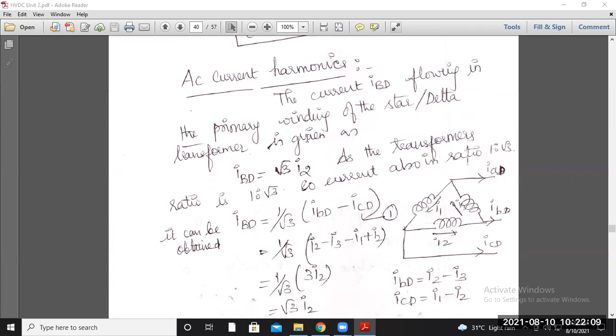So here it is given that the transformer's ratio is 1 to root 3, for the star to delta connection, that is the second 6-pulse bridge converter. So the current will also be in the ratio of 1 to root 3, which can be written as IBD equals 1 upon root 3 times IBD minus ICD.